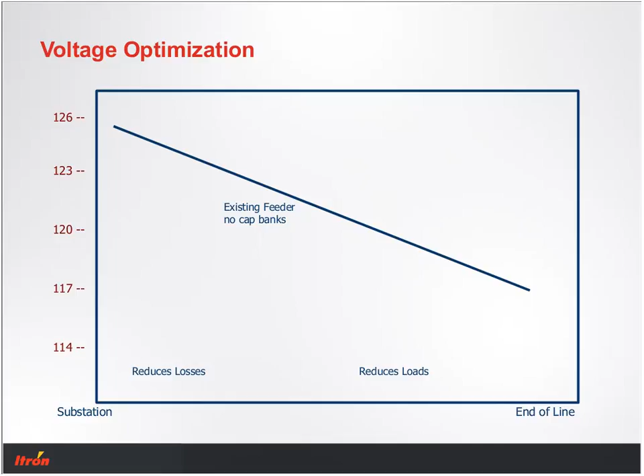Now, why is that? Well, part of the reason that there is such a drop involves reactive flow on the circuit, which basically is a need. You solve that by placing cap banks out there and bringing your power factor to unity. By doing that, by adding cap banks, I can flatten that curve. So basically now I've reduced that drop from 126 to 117 to 126 to approximately 122. So now I have a 4-volt drop end to end versus a 9-volt drop.